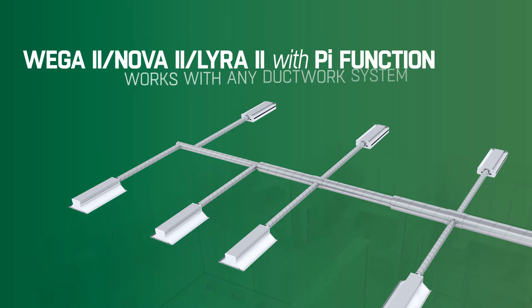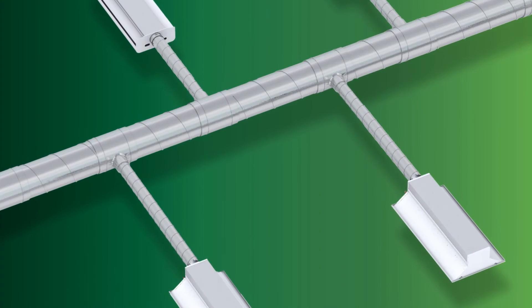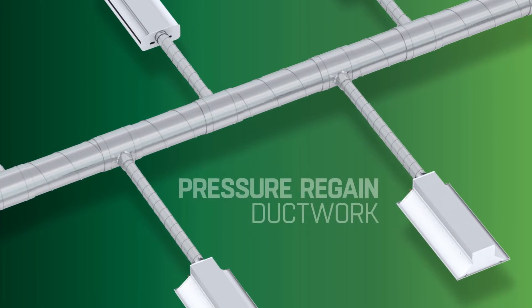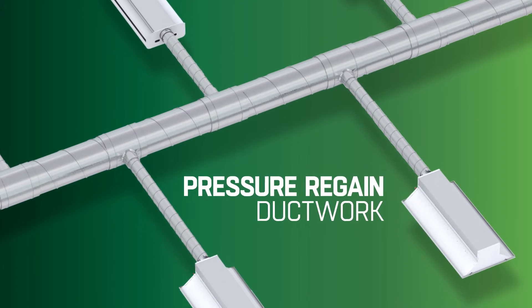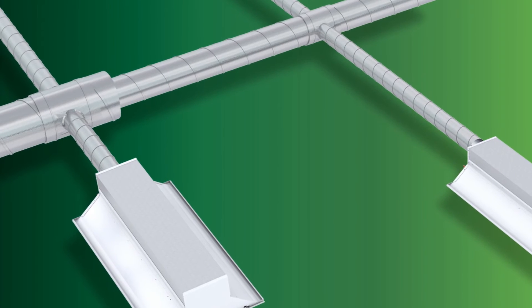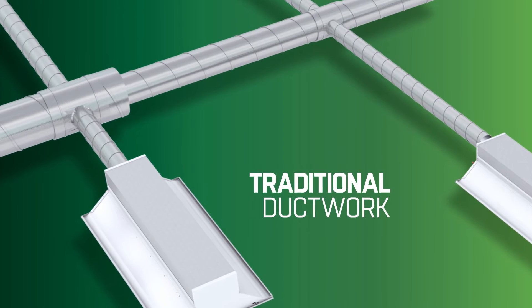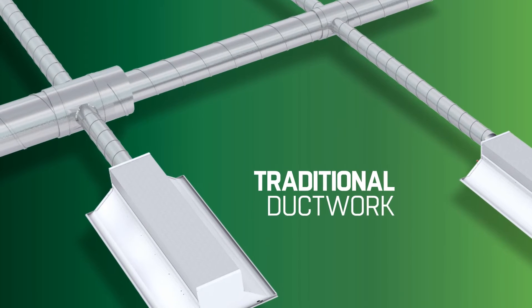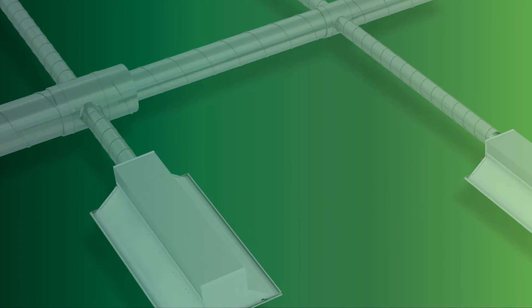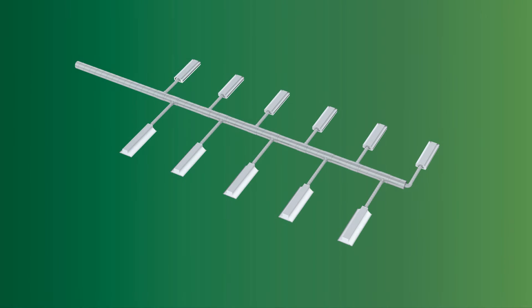With Wega II, Nova II and Lyra II, this energy saving technique does not require any brand new ventilation systems with pressure regain ductwork. Thanks to the unique self-balancing PI function of our new chilled beams, DCV can now be utilised in any ventilation system, even with traditional ductwork. Our new chilled beams can be ordered with the PI function integrated, but it can also be added to standard versions later on in a staged DCV upgrade.